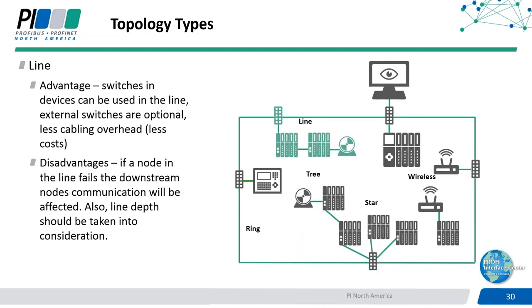Next we have a line topology. This is possible with PROFINET as most devices have a built-in switch, allowing you to daisy chain or do a direct run between your controller to the devices. An advantage of this is the cost can be reduced since external switches are now optional and there's less cabling overhead. Of course, one disadvantage of line topology is if a node fails in the line, the downstream nodes are affected and can no longer communicate. We also need to consider the line depth, and we'll discuss that further in an upcoming section.